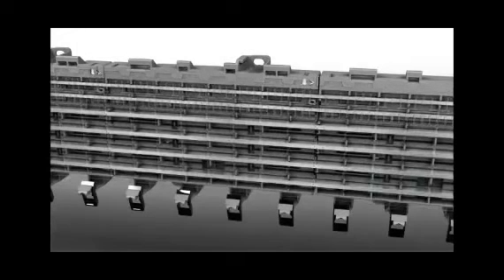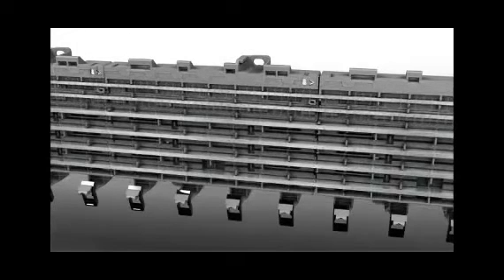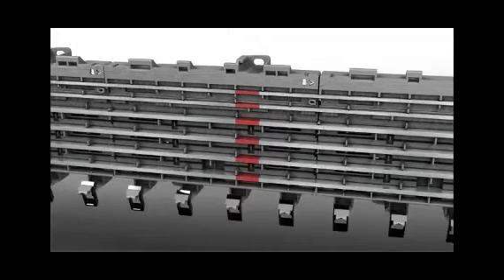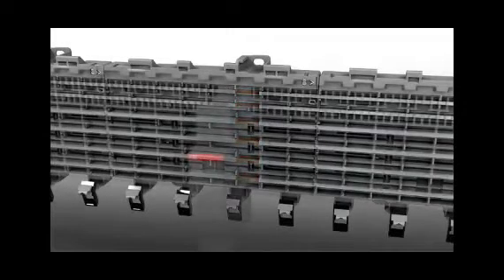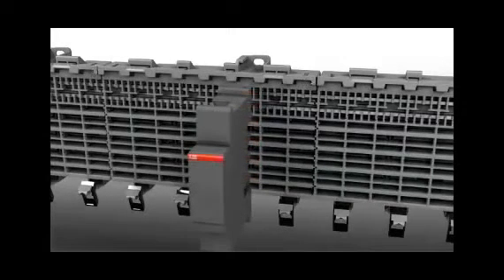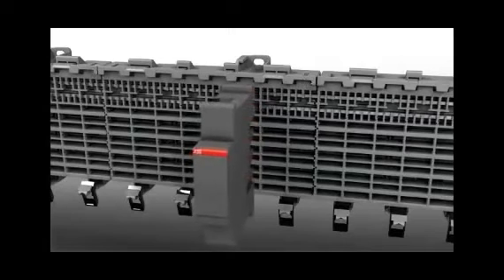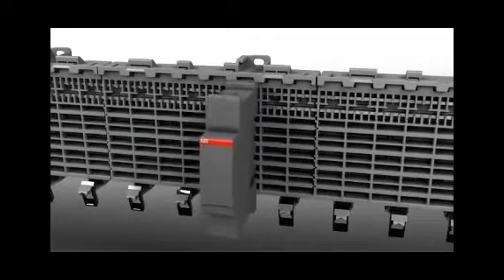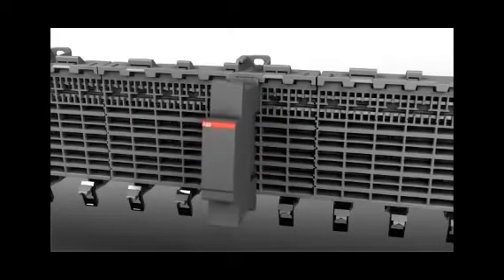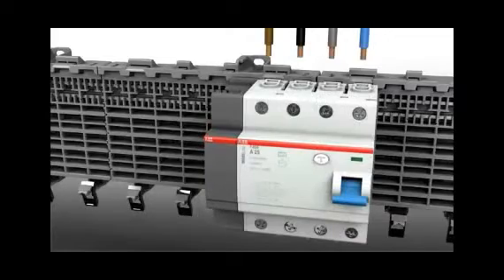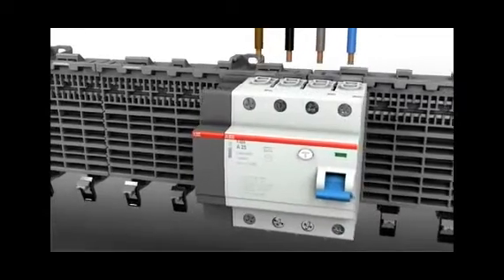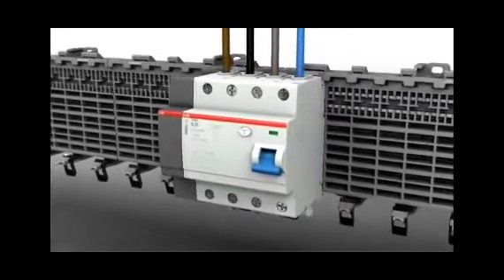Bus bars can be isolated. Using an isolator, this allows you to create different circuits on the sockets. By doing this, you can create groups that are protected against residual currents, for example. In such cases, power is supplied via residual current circuit breaker.